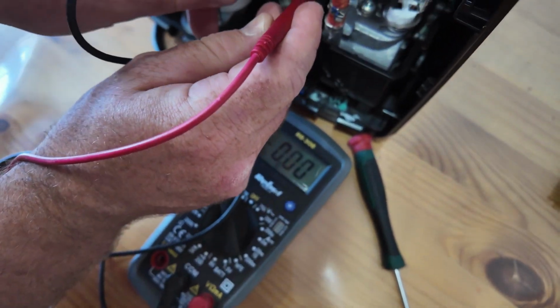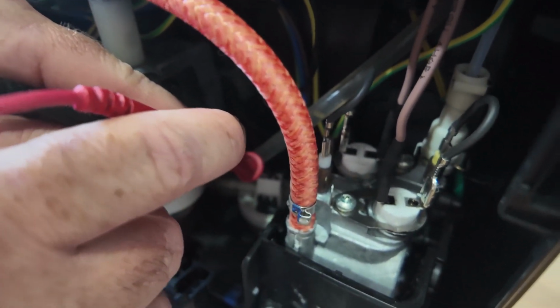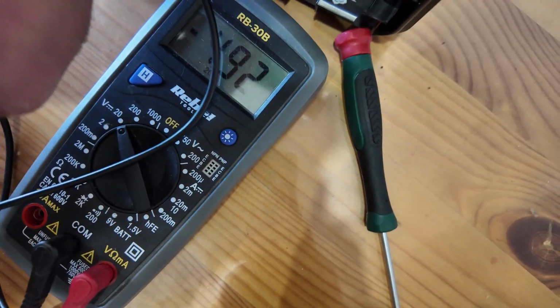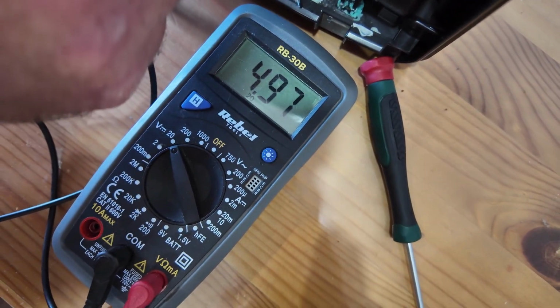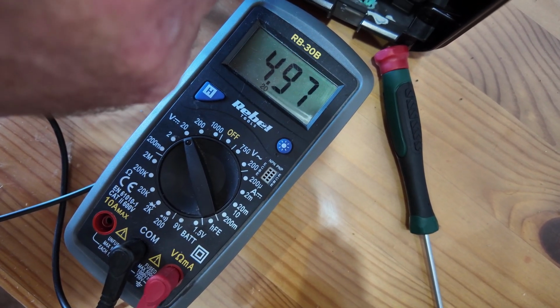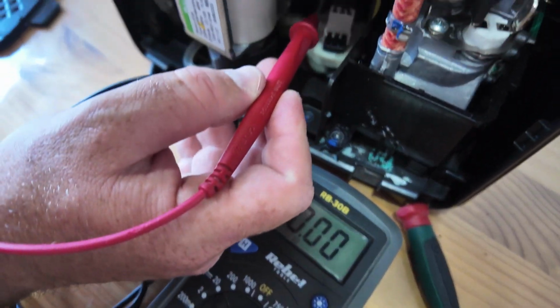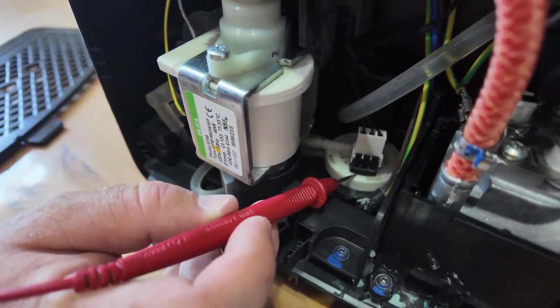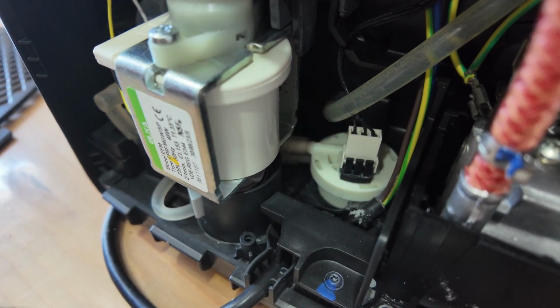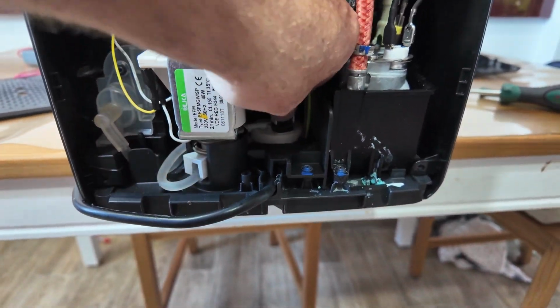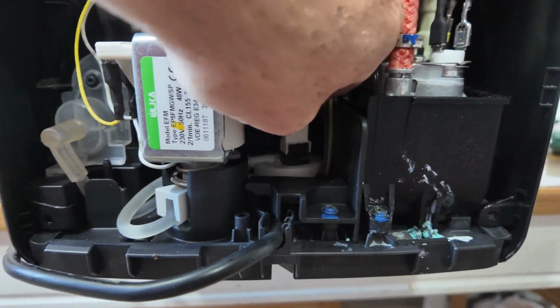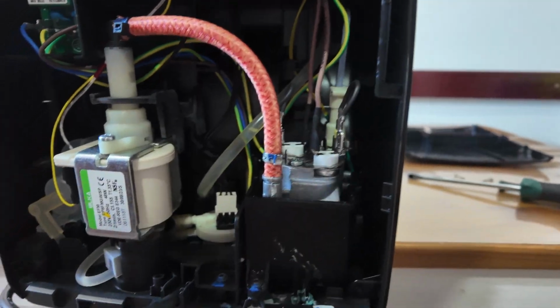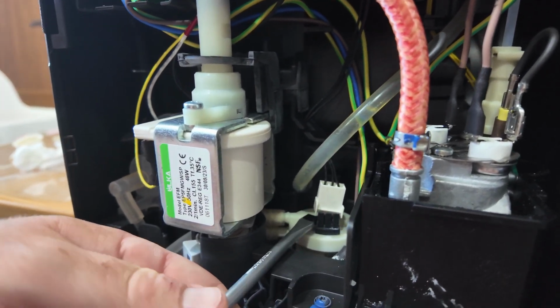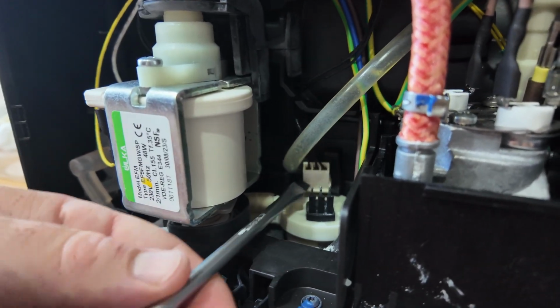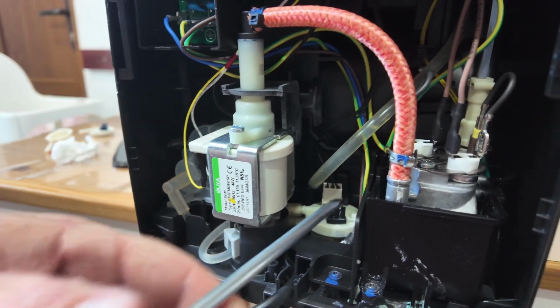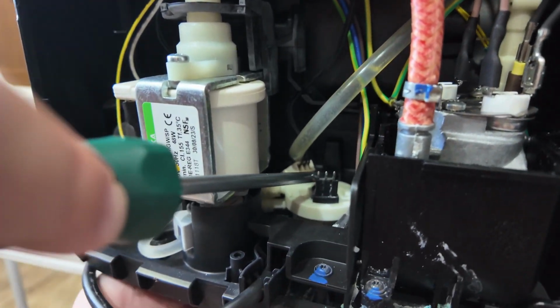If we check, this flow sensor should send a signal of 5 volts. And if we check another cable, then we should see at least something changing, something going on with the signal. And the signal seems to be stuck on those 3 pins. So I suspect this flow meter is the bad one and needs to be replaced. So we will remove this cable which is connecting. And if you are not able to with your hand, then use a flat screwdriver. Then you have a pin in the back of it, but you can push it.